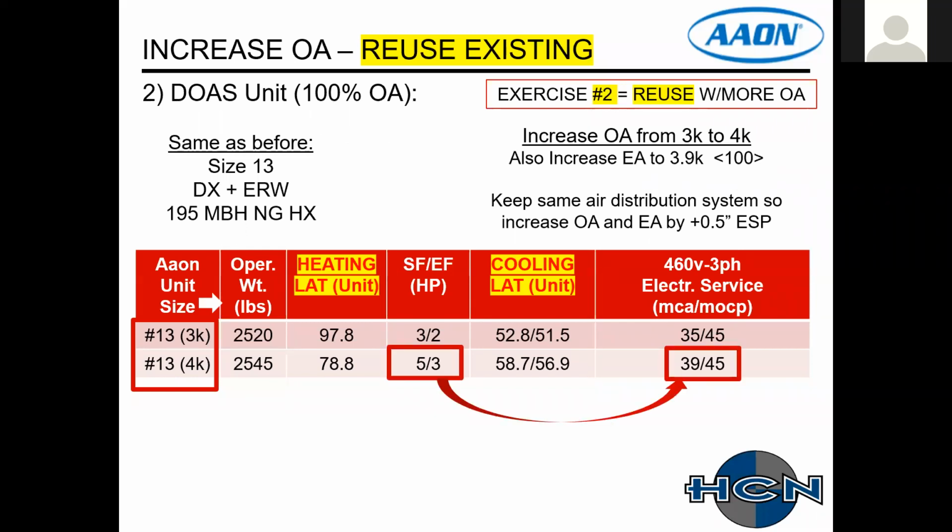temperature. What has happened is that with the additional CFM as well as the additional static pressure, I'm going to require a larger supply and exhaust fan. That larger supply and exhaust fan you can see as increased MCA. That's obviously probably not a problem.